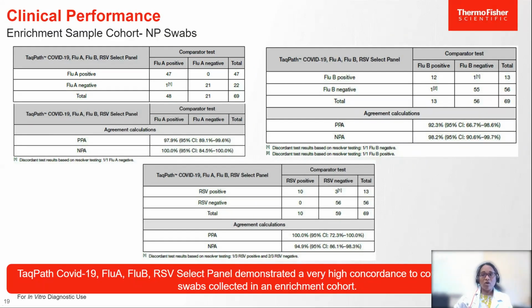We found that of the 69 samples that were collected for NP, we again saw concordance with the comparator device, with a PPA of 97.9% for flu A, 92.3% for flu B, and 100% for RSV. Again, very, very high PPA. And you can see the NPA numbers also very high, greater than 95% for all 3 targets. As I had mentioned, there were no SARS-CoV-2 samples collected during the enrichment phase because we had already met our numbers for SARS-CoV-2.